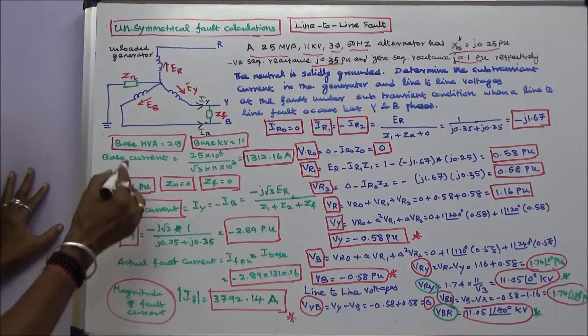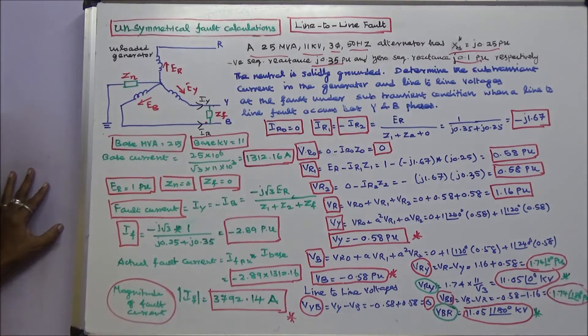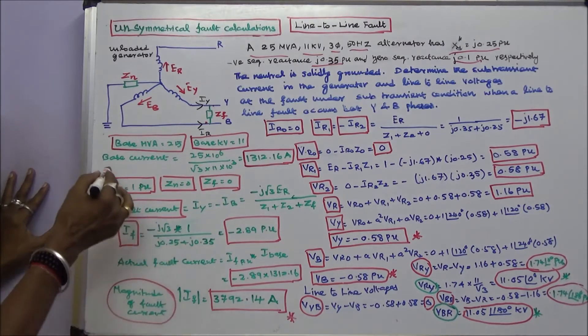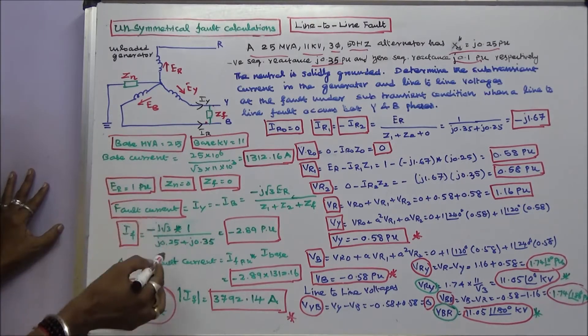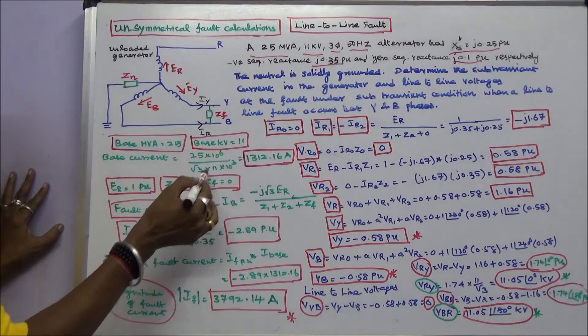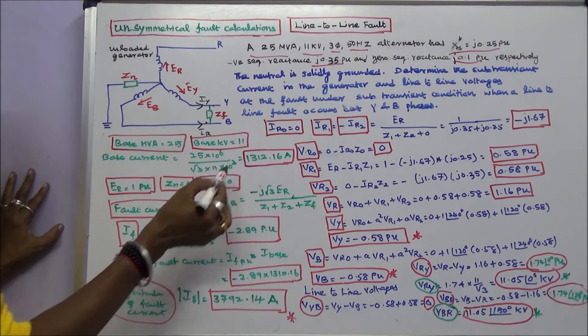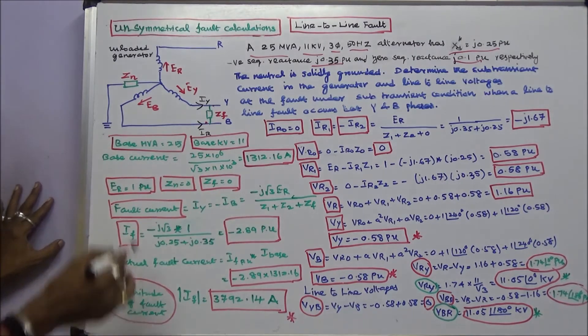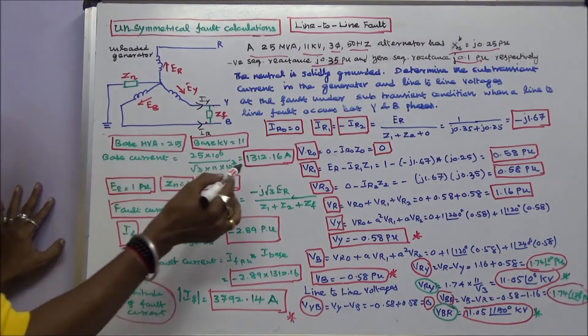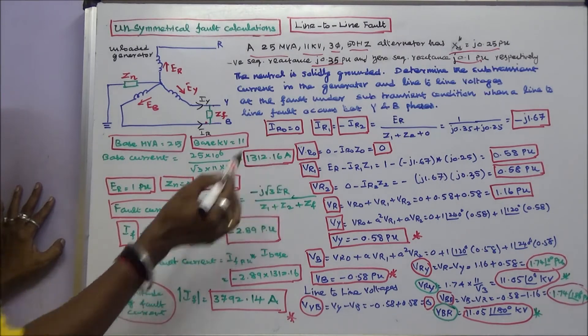We choose base MVA equal to 25, base KV equal to 11. We can find base current: that is equal to 25 into 10 power 6 divided by root 3 into 11 into 10 power 3. Base current is 1312.16 amps.